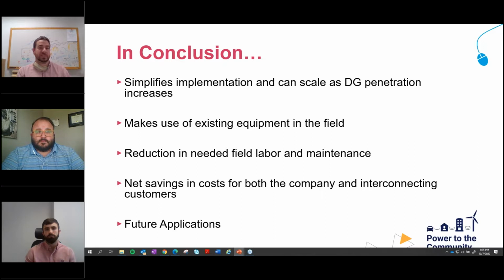So we want to use Sensus and the automation control system to remotely monitor the load or generation coming out of that DER site and kick on the switch capacitor bank. That way you're not limited - you don't have to have that switch capacitor bank installed upstream from the DER site. It could be downstream, it could be wherever, and they'll be tied together. Sun comes up, switch cap goes in; sun, cloud goes by, switch cap opens up - so it allows them to follow each other.